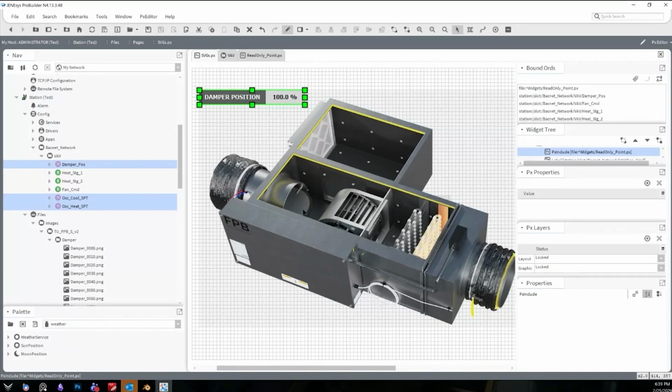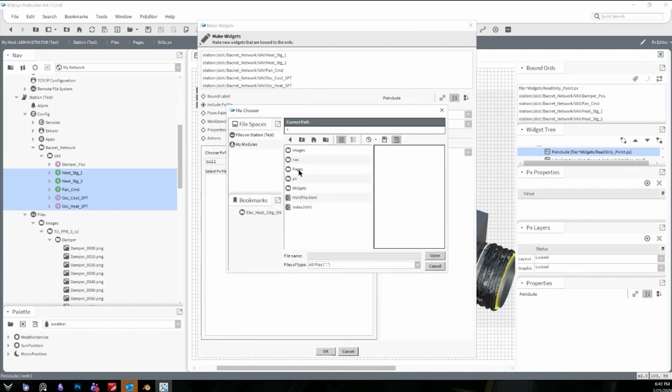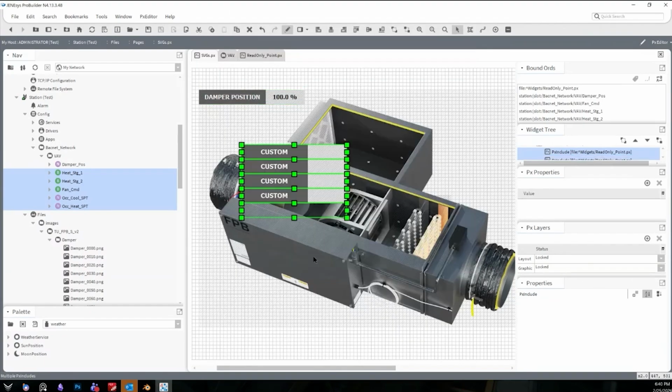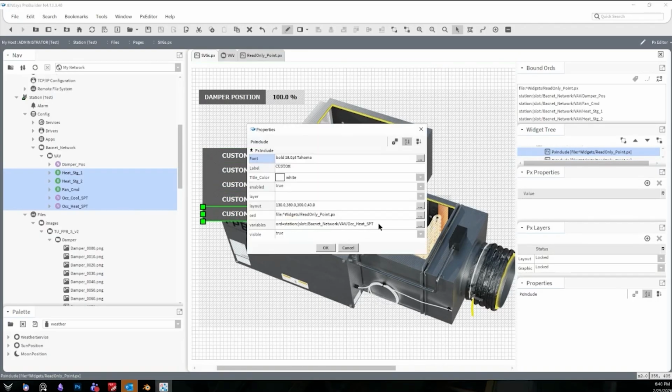There's a lot of things you can do. You can create set buttons and action buttons, and then the beauty of something like this is you can just drag all your, say, read only points, for instance. You can drag them all in. And I do these for call outs on floor plans, right? So I'll just drag them all out in one fell swoop, all the fan powered boxes for that floor, maybe in chunks of 5 or 10, so they fit on my screen when I drag them in. That allows me to bring all these in immediately. And they all have custom names.